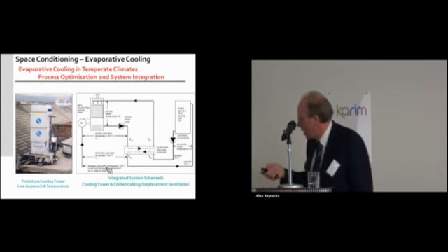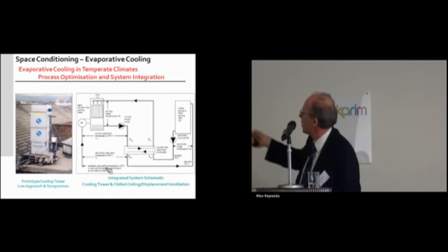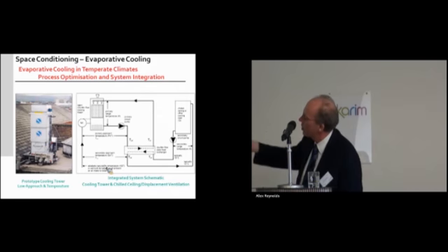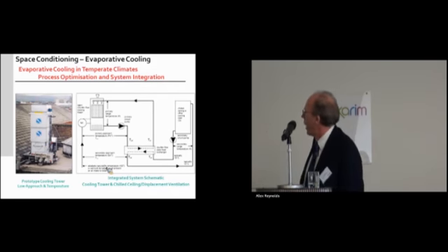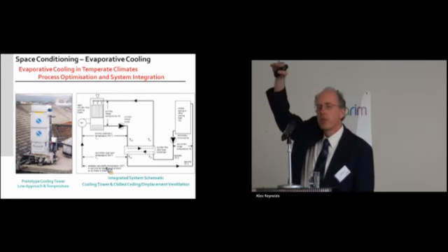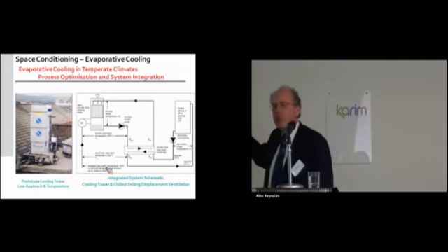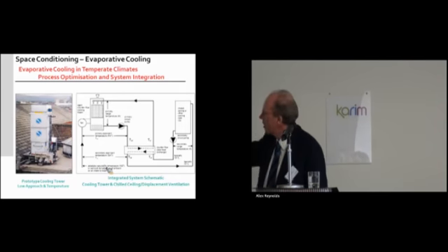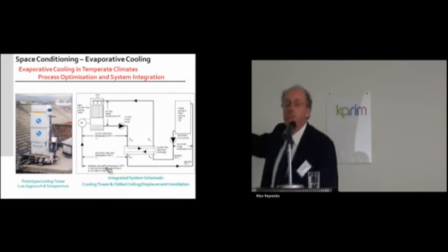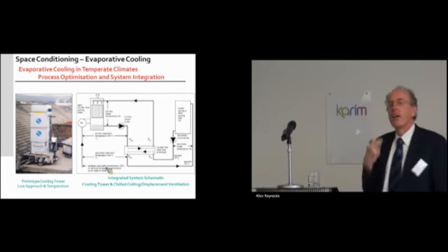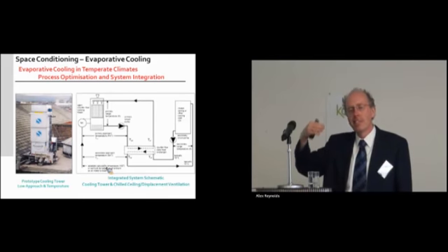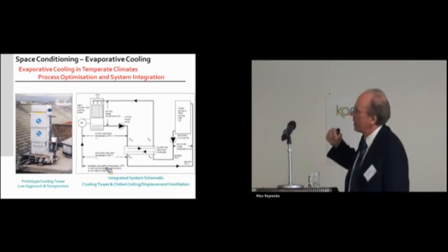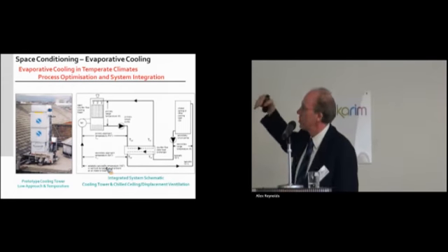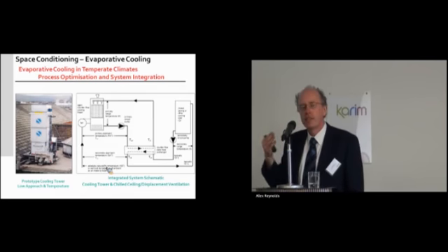And we achieved that. So essentially what we're doing is, this here represents the building. There's a plated heat exchanger between the primary loop, which goes through the cooling tower, and the building here. And the water normally returns, it's circulated, remember, through chilled panels in the ceiling, and it returns at about 18 to 20 degrees. And then through the primary and secondary system, mainly through the cooling tower itself, it's cooled back down and it's reintroduced to the building at about 15 degrees centigrade. Why do you want to do this? Well, in air conditioning systems, you normally produce chilled water at about 6 degrees centigrade. And the potential advantage of this is under optimized operation conditions, we can get COPs between 6 and about 16. So there is a potential energy saving which is associated with this.